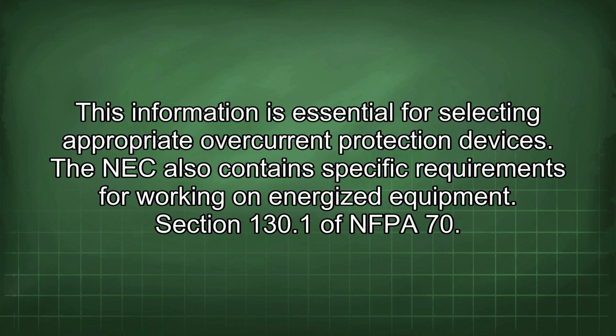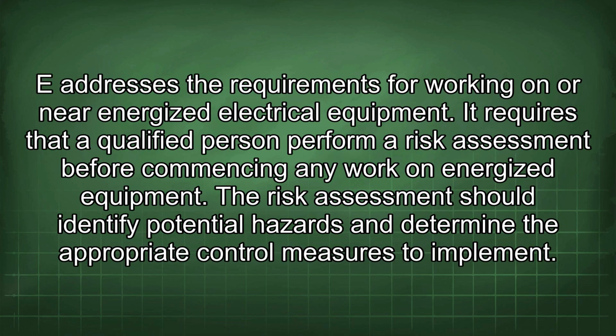The NEC also contains specific requirements for working on energized equipment. Section 130.1 of NFPA 70 addresses the requirements for working on or near energized electrical equipment. It requires that the qualified person perform a risk assessment before commencing any work on energized equipment. The risk assessment should identify potential hazards and determine the appropriate control measures to implement.